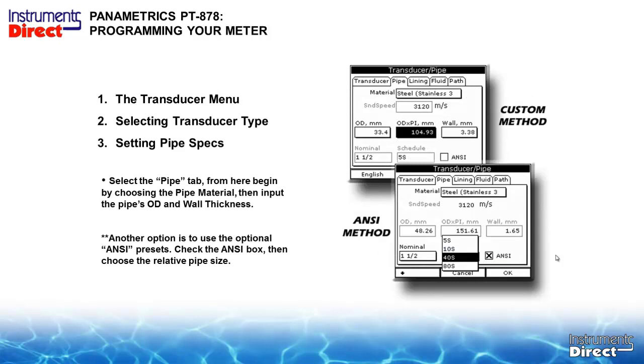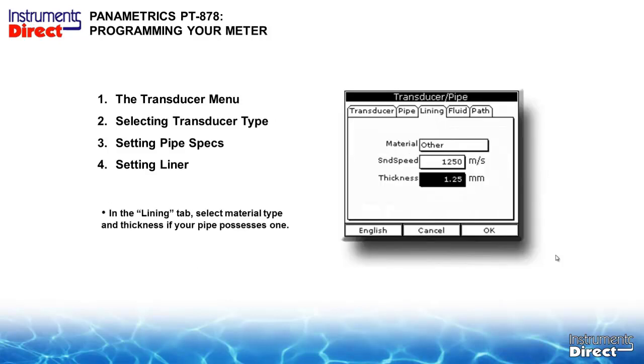And this is where people make their biggest mistake. Bad data in, bad data out. So you must put in the correct pipe OD, and if you're not really sure, take your tape measure, wrap it around, divide it by pi, 3.14, and you'll have your pipe OD. You can flip the ANSI switch there and put in a nominal pipe size, which can help you, but you've got to put in the right pipe data in order to have this thing calculate properly.